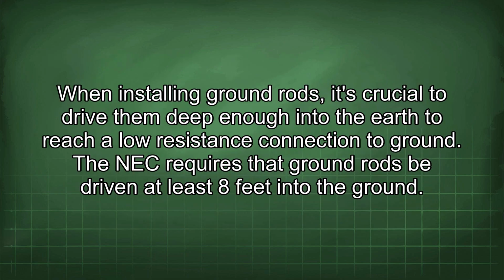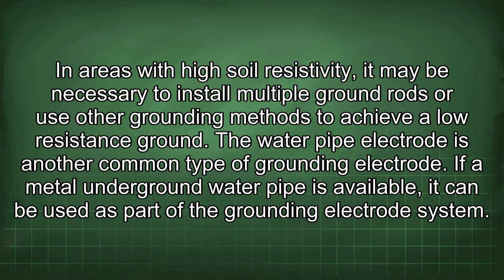When installing ground rods, it's crucial to drive them deep enough into the earth to reach a low resistance connection to ground. The NEC requires that ground rods be driven at least 8 feet into the ground. In areas with high soil resistivity, it may be necessary to install multiple ground rods, or use other grounding methods to achieve a low resistance ground. The water pipe electrode is another common type of grounding electrode.